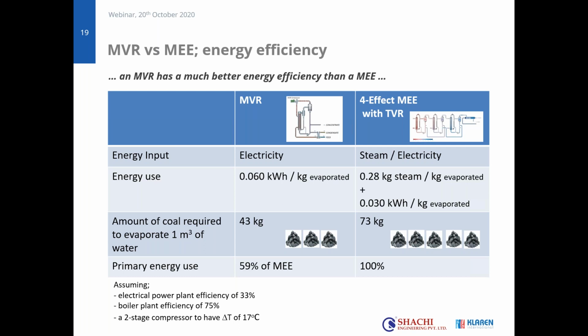If we then convert both the energy inputs, steam or electricity, to coal with some simple calculations, assuming an electrical power plant efficiency and an efficiency of a boiler, and a design with a two-stage compressor that has a certain delta T, you could back calculate how much coal, how much primary energy I need to convert to evaporate 1 cube of water.